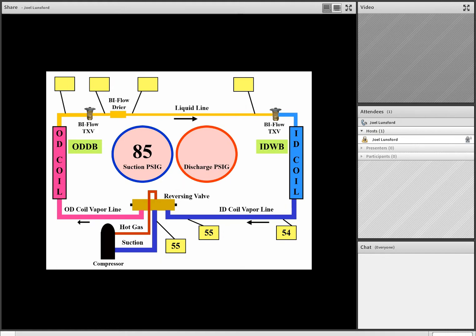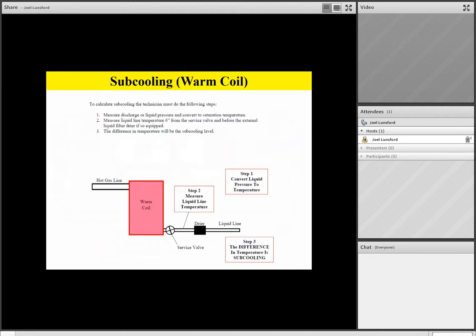And subcooling. Let's review subcooling one more time before we get into diagnostics. Subcooling always applies to the warm coil. And if the subcooling is high, that coil is flooded. If the subcooling is low, the warm coil is starved. If the subcooling is about 10 to 15 degrees in the cooling mode, we'll consider that normal subcooling. If the subcooling is about 15 to 25 degrees in the heating mode, that will be considered a normal range.